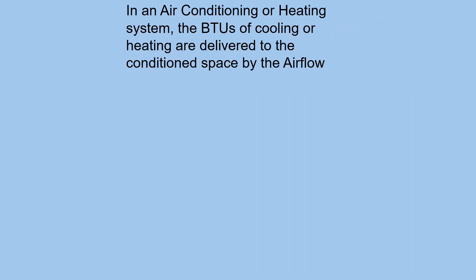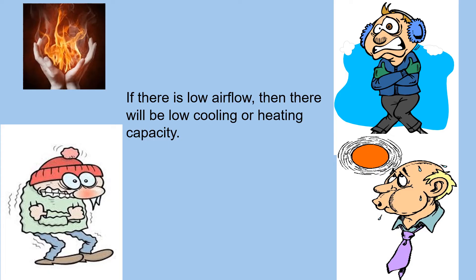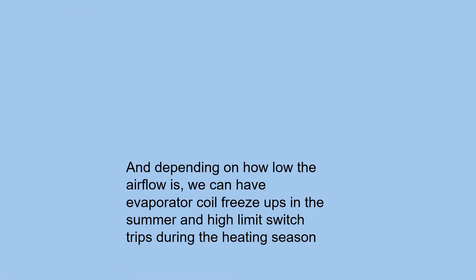In an air conditioning or heating system, the BTUs of cooling or heating are delivered to the conditioned space by the airflow. If there is low airflow, then there will be low cooling or heating capacity. And depending on how low the airflow is, we can have evaporator coil freeze-ups in the summer and high limit switch trips during the heating season.